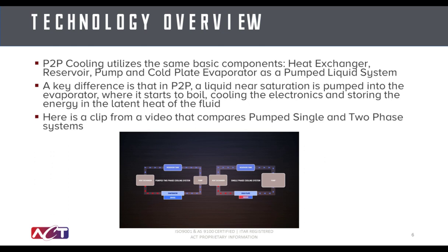Comparing pump two-phase to single-phase solutions, if you were to look at the systems from the outside, they'd look nearly identical. They both include a heat exchanger, a reservoir, a pump, and a cold plate. The difference between a pump two-phase system and a single-phase system mostly relies on the size of the pump. Because you're utilizing the latent heat of the working fluid, you can get away with significantly less pumping power. We'll provide some examples of exact numbers for that later on. Here's a quick video to demonstrate the differences between pump single-phase and pump two-phase.